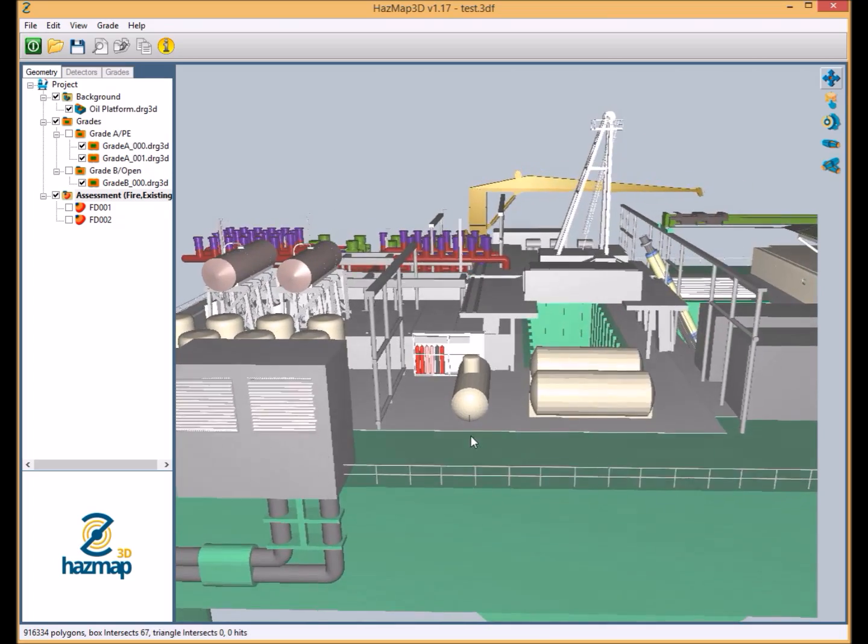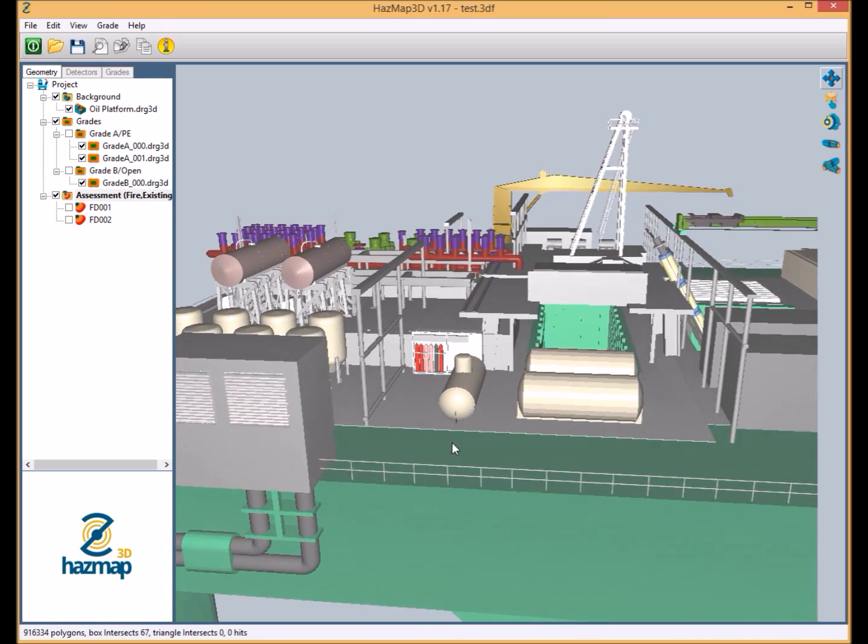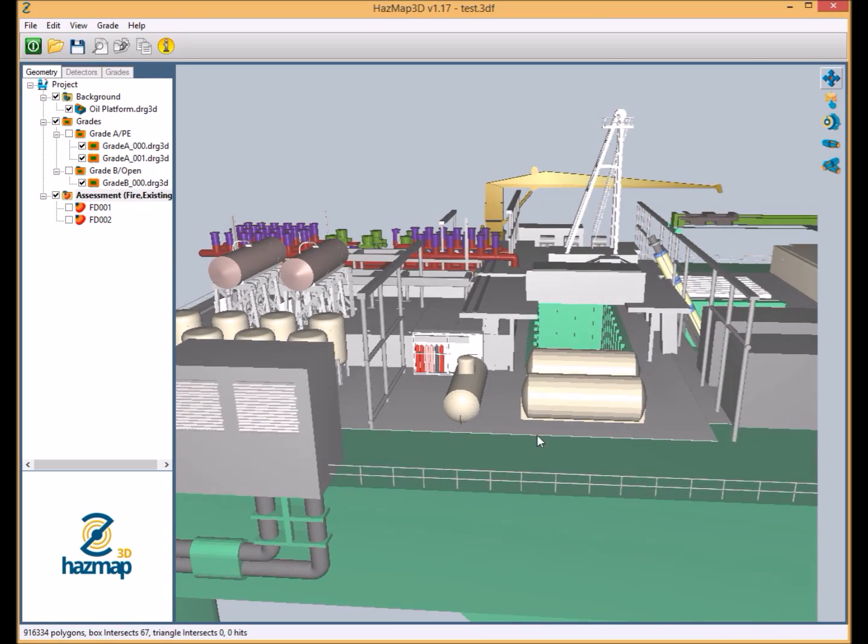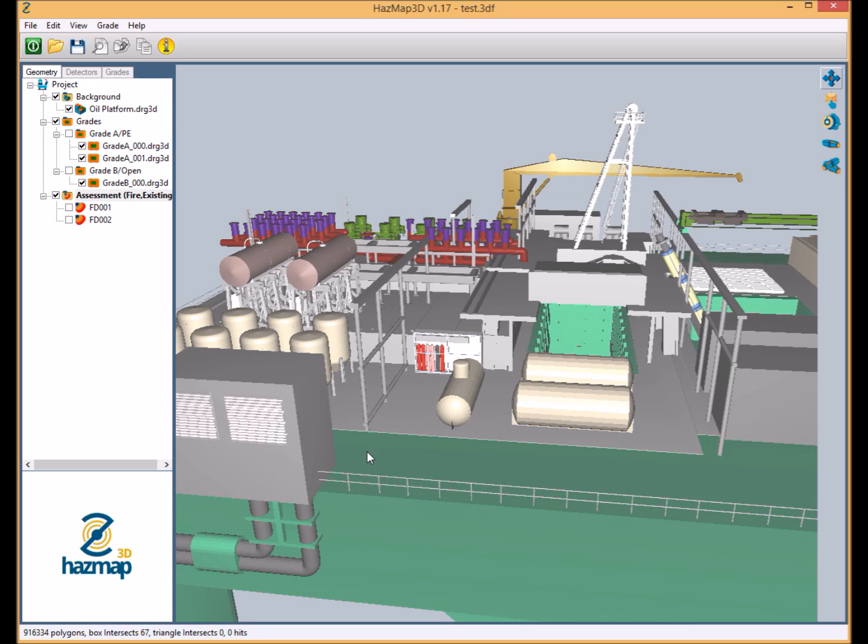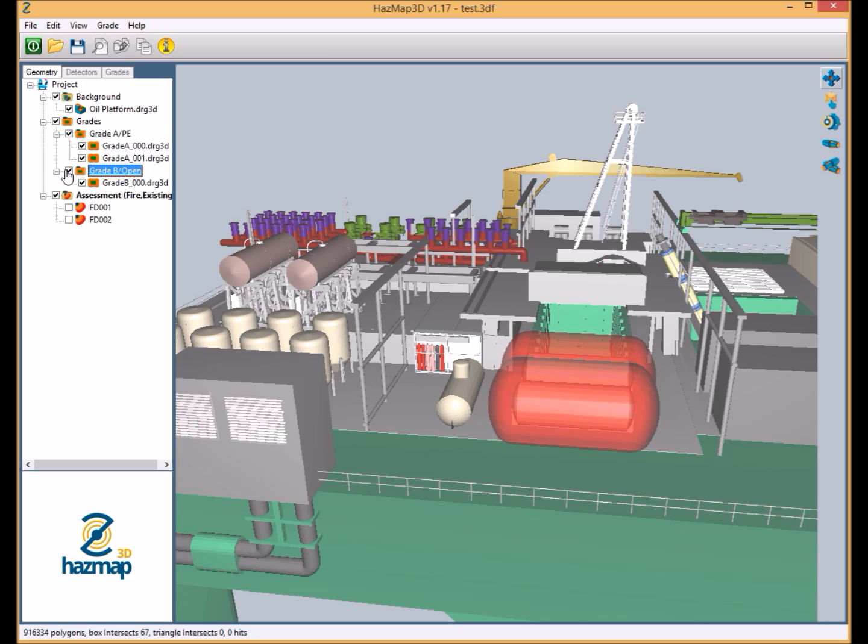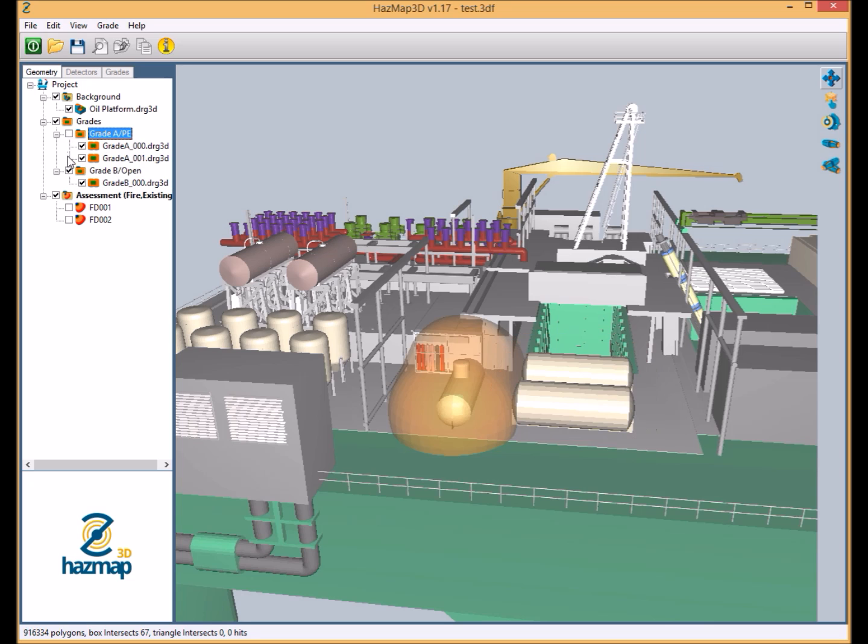So the first thing we need to do to run our assessment is get an idea of the shoebox volume that we want to analyze. So in order to do that, we need two coordinates: the coordinates of the origin and the coordinates of the extent that we would want the assessment to cover. Obviously, as far as the assessment is concerned, because it's flame detection, we're not looking at the entire volume. We're looking specifically at the previously graded areas, as we saw earlier on when we set our hazard grades. But we still need to specify that shoebox volume.